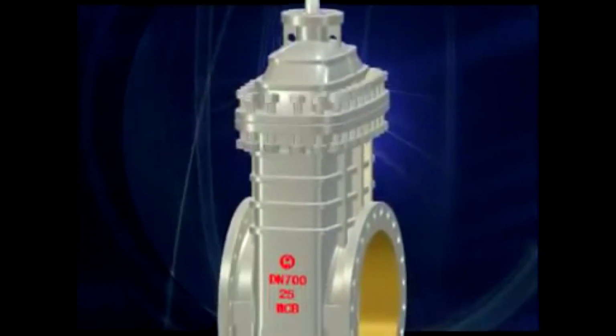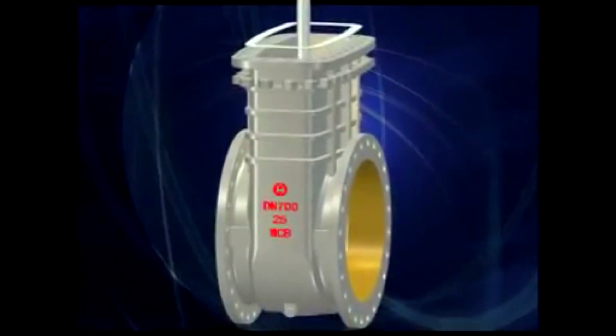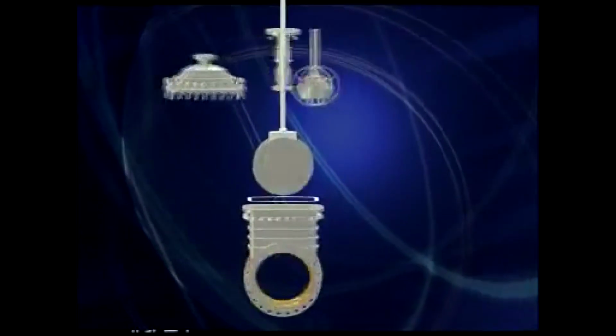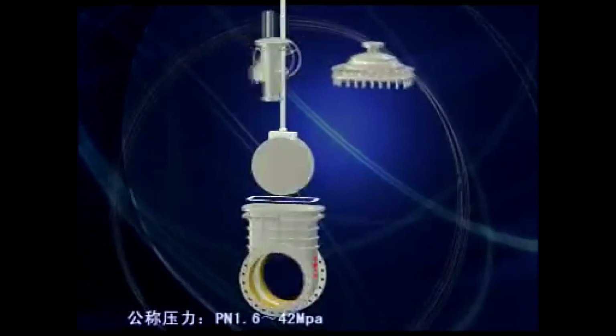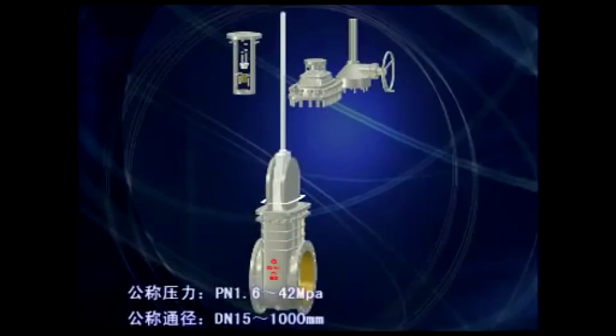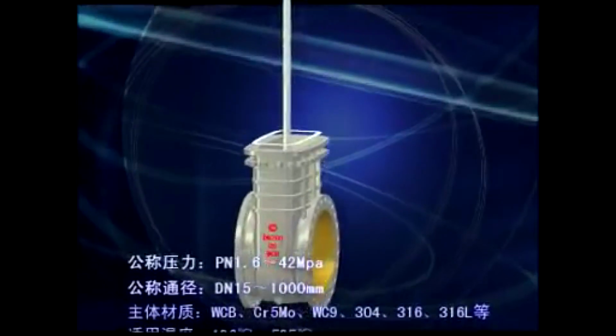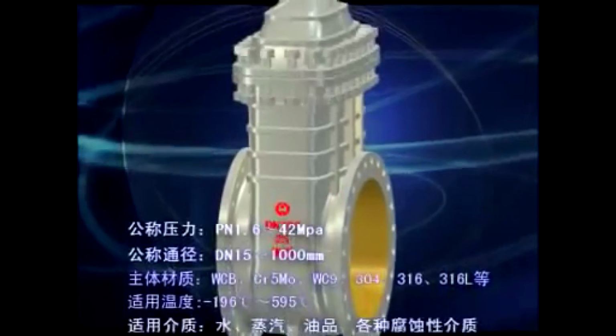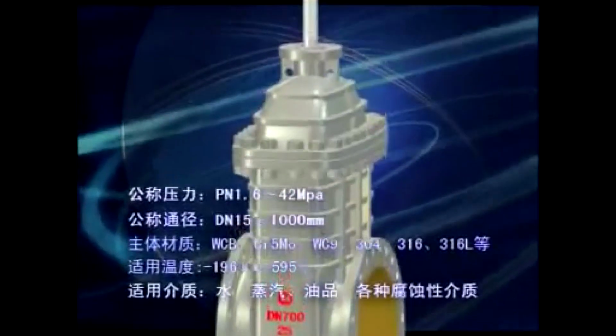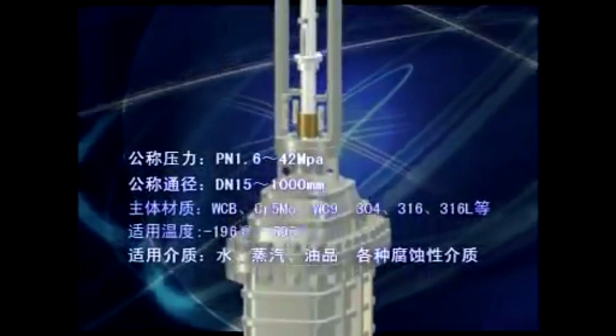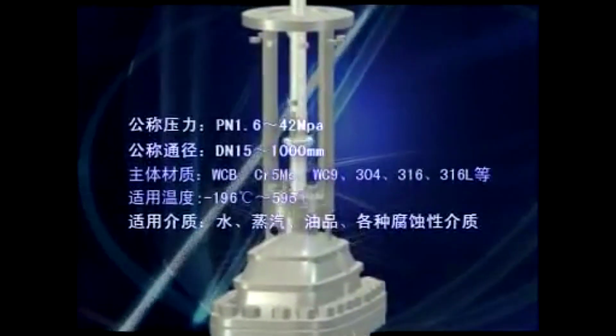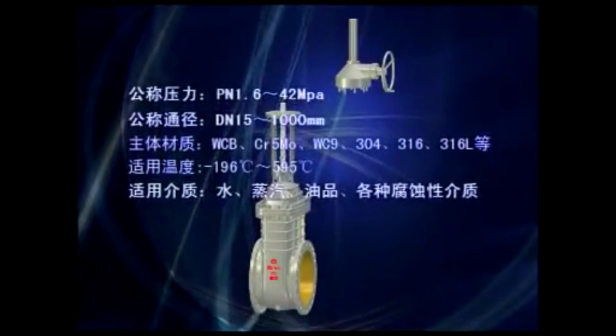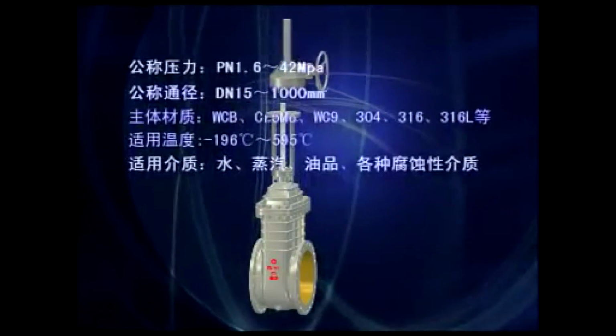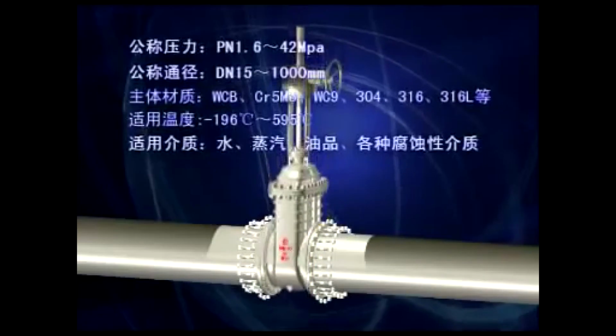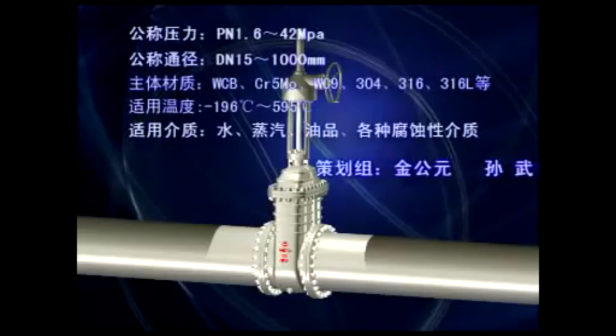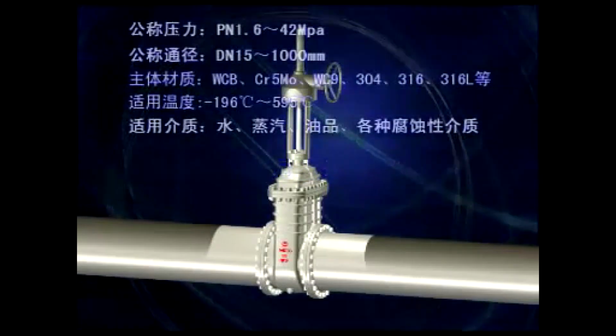The applicable scope and main technical parameters for this product: nominal pressure from PN 1.6 MPa to 42 MPa. Inside nominal diameter, DN 15mm to 1000mm. Main body material, WCB, Cr5Mo, WC9, 304, 316, 316L and so on. Applicable temperature from minus 196 degrees centigrade to 595 degrees centigrade. Applicable medium, water, steam, oil product and kinds of corrosive medium.